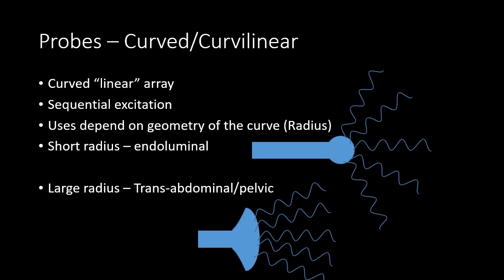The curved probe, sometimes referred to as a curved linear probe, is truly a linear array oriented along a particular radius, with sequential excitation of the piezoelectric crystals. Unlike a linear array with a flat transducer surface, the curved probe has a particular radius. The geometry of our image will depend on that radius. Short radius probes — such as endoluminal or transvaginal probes — provide a very wide field of view from a smaller probe. A traditional large radius curved array is used for transabdominal and pelvic imaging, generating a wide field of view with more rectilinear geometry.